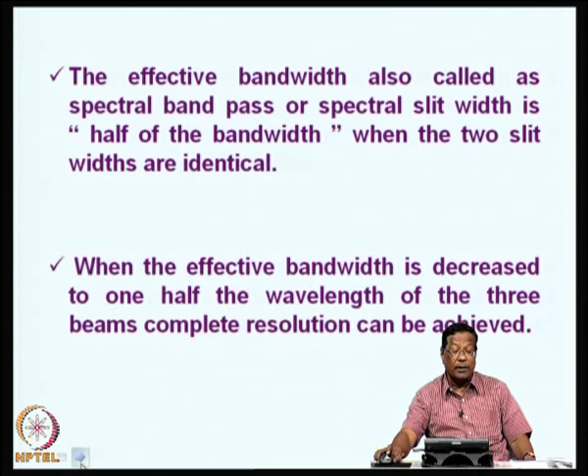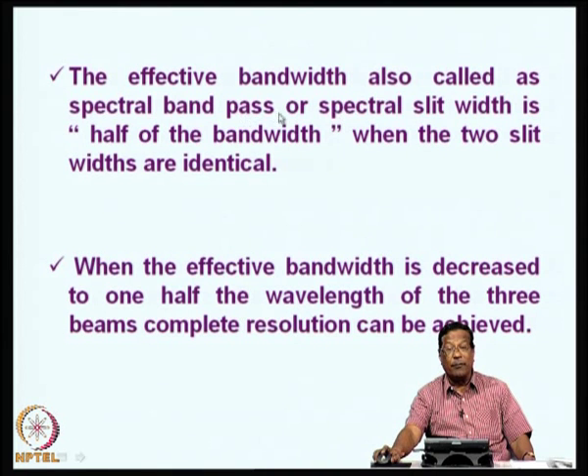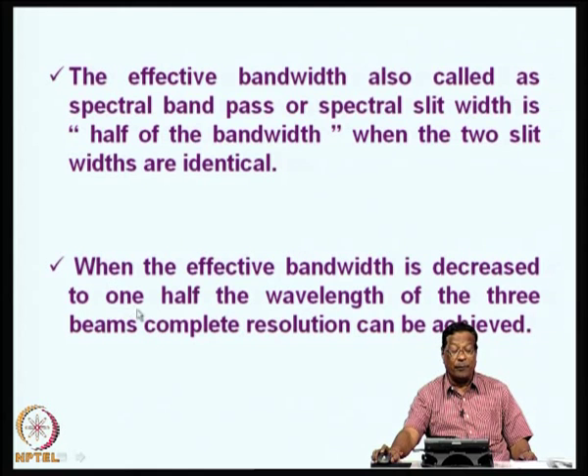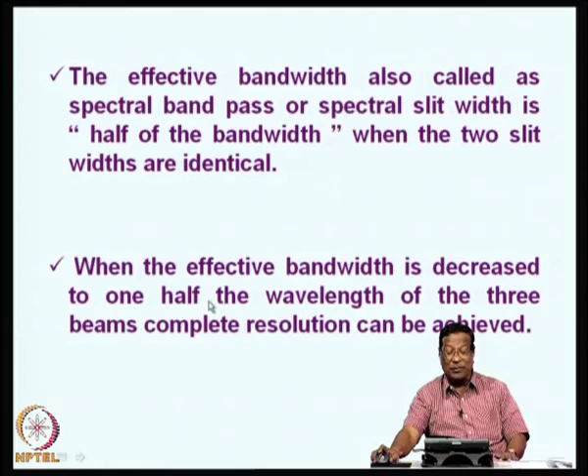The effective bandwidth is also called spectral band pass or spectral slit width. It is half of the bandwidth when the two slit widths are identical — it is very important that two slit widths should be identical, otherwise you will not have a good spectrum. When the effective bandwidth is decreased to one half the wavelength of the three beams, complete resolution can be obtained. Otherwise, there will always be bunching of the radiations, and it would not give you spectral purity.